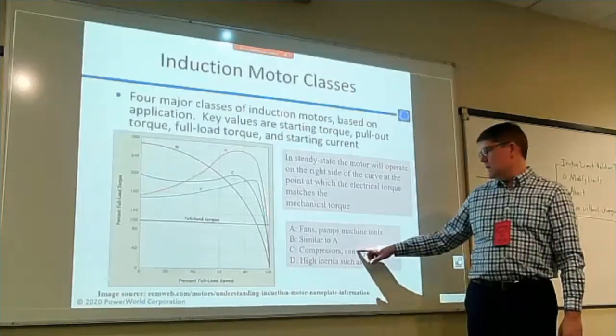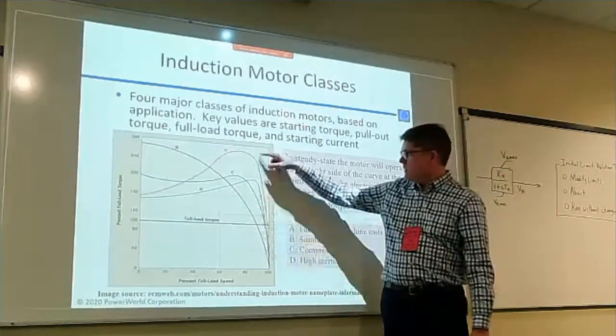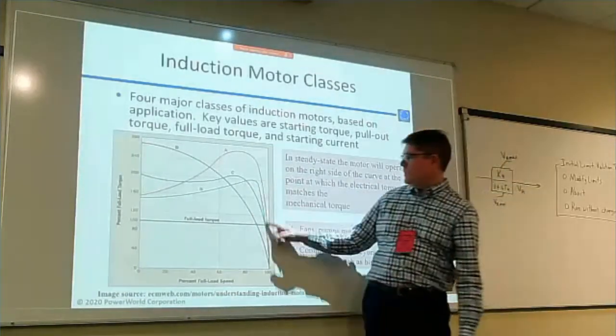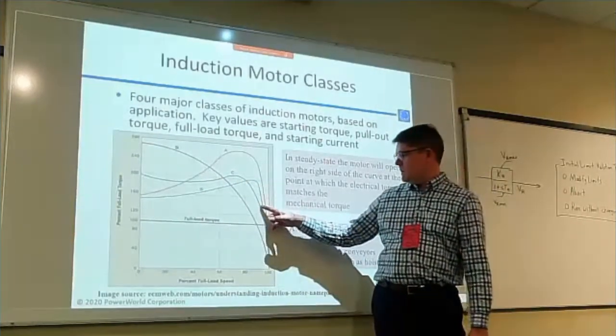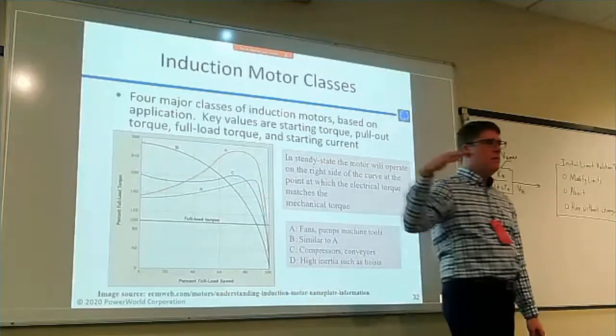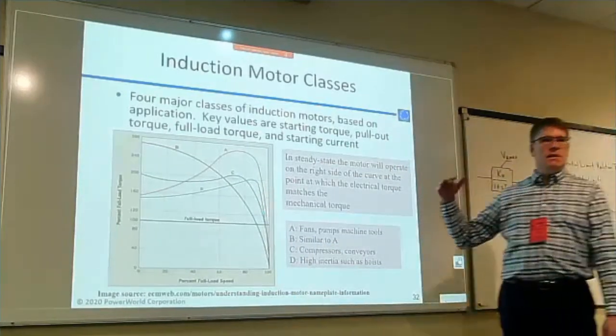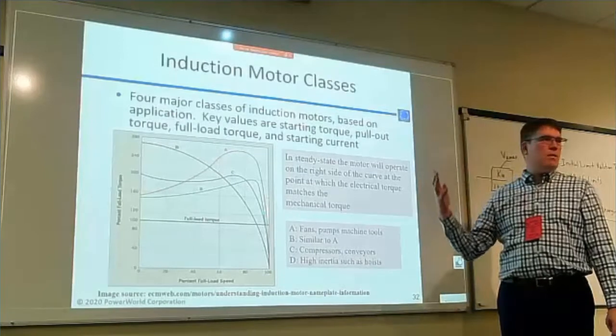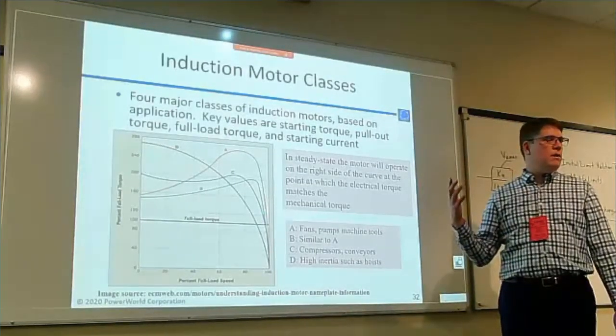B is similar to A, but just lower. And the C values are the compressor motors. I'm guessing that's because as the speed drops on a compressor, you want the power to stay up as long as you can, since shutting off a compressor means you have to wait a while before turning it back on.